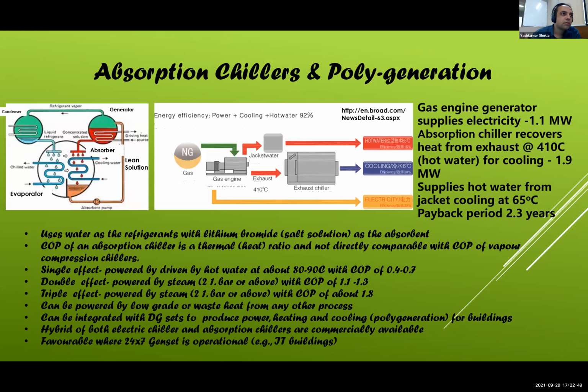The last slide I have is absorption chillers and poly generation. Absorption does not use any refrigerant per se, but it uses either water or ammonia as the refrigerant. If you take lithium bromide water, it uses water as the refrigerant, and it is similar to mechanical vapor compression, but then you are dealing with a pump rather than a compressor.